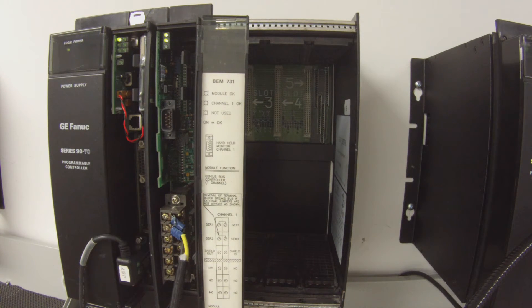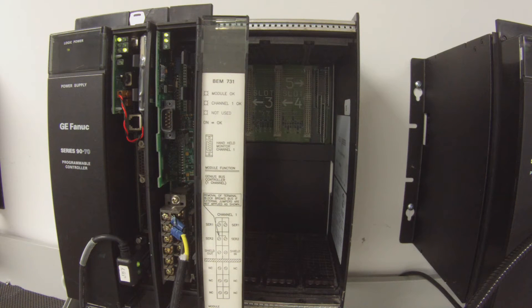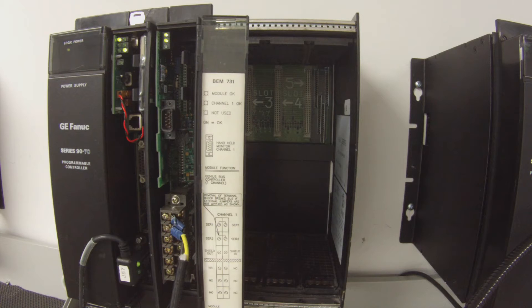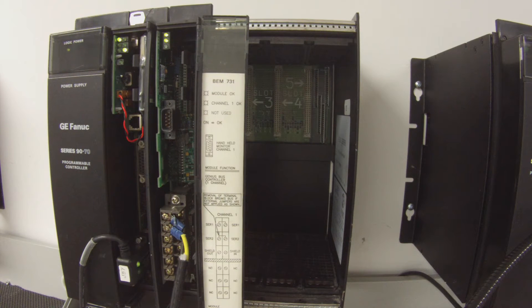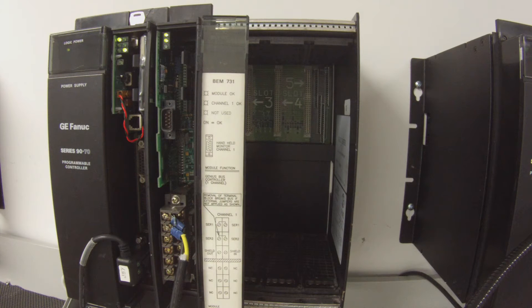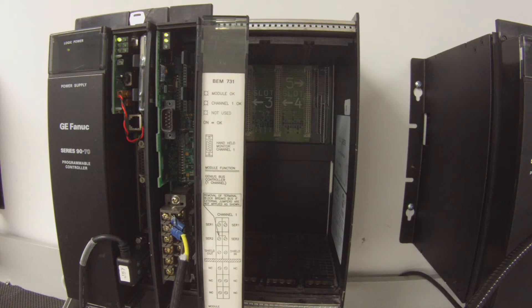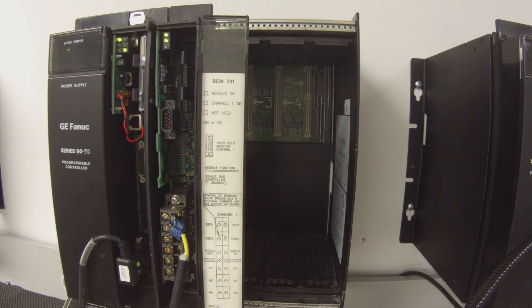And then I'm going to hit Download and Run. When it asks me what exactly I want to download and run in just a second here, I'm going to select Configuration and Logic. So Hardware Configuration and Logic. The top two choices. And don't click anything else. We don't want to write this to permanent flash memory. OK.